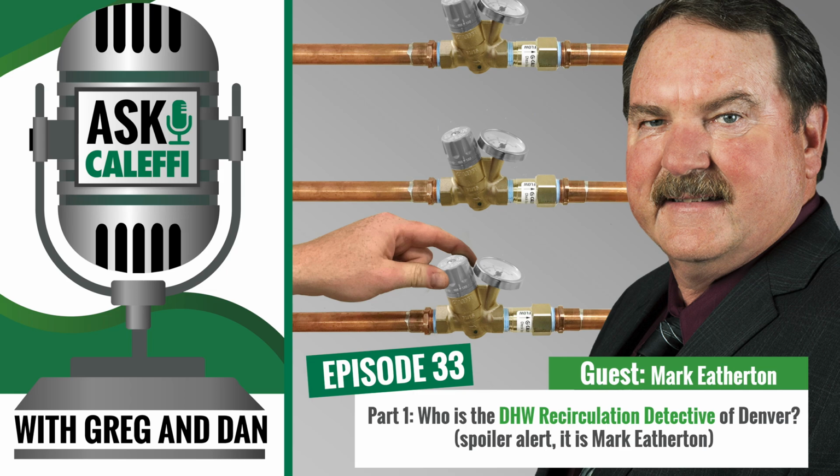And it's amazing what we're seeing in the field as it pertains to these domestic hot water supply and circulation return systems. I was called out on an emergency active leak in the mechanical room this week on a job that we had just done a total retrofit of, and got in there and saw that it was the circulation return, and it had pinholed a couple of inches after a fitting. I asked the maintenance man, do you have pinhole leaks springing up in your building? And he said, everywhere. Wow. And he said, only on the smaller lines. And I said, only on the domestic hot water?